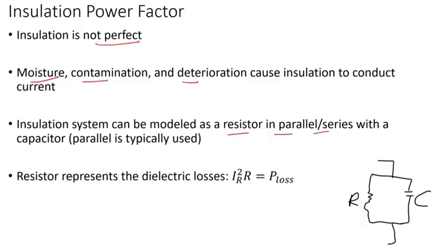With a capacitor, and typically parallel is used. So what you see here, you have the capacitor in parallel with the resistor. The resistor represents the dielectric losses. We know there should be no current flowing, but because insulation is not perfect, there will be some losses.